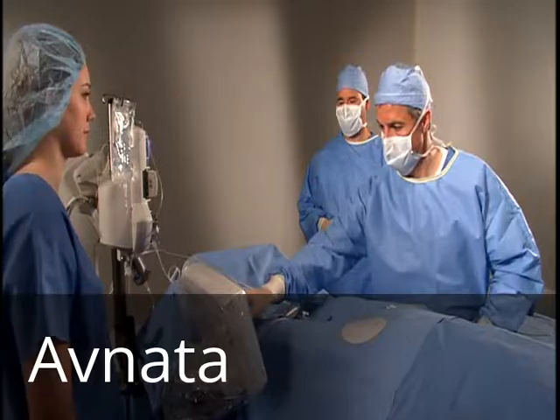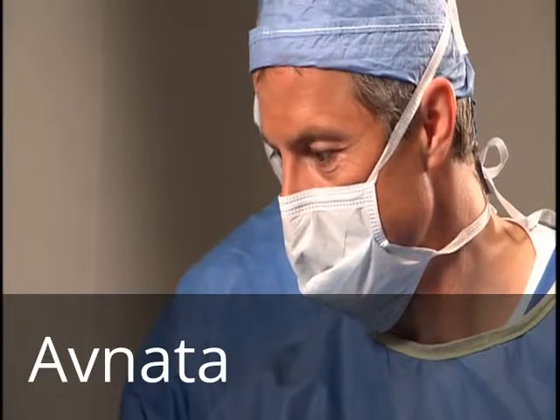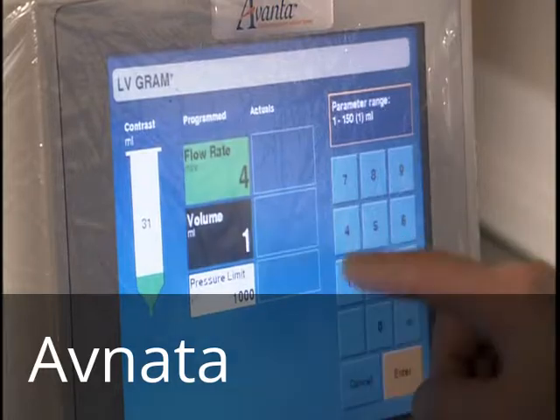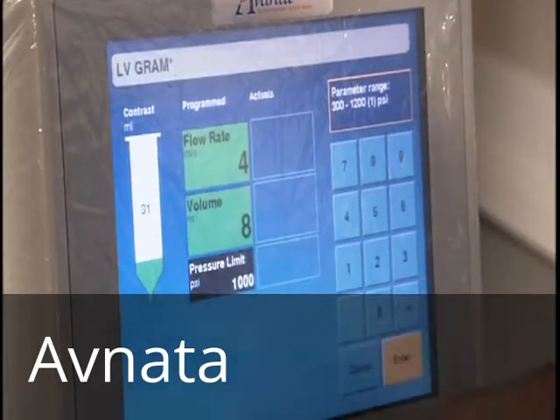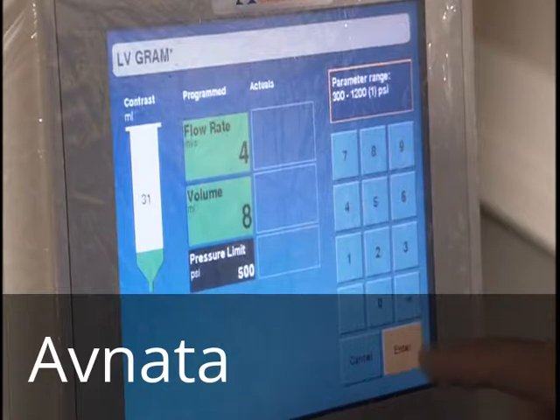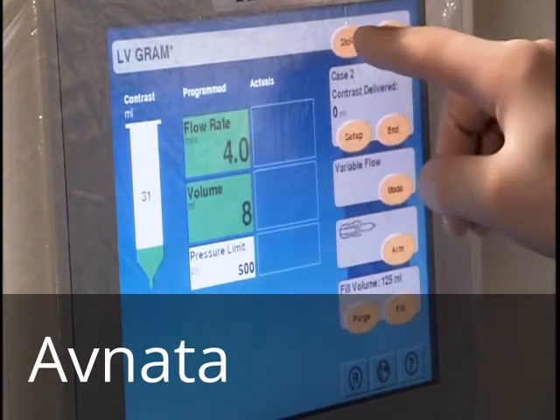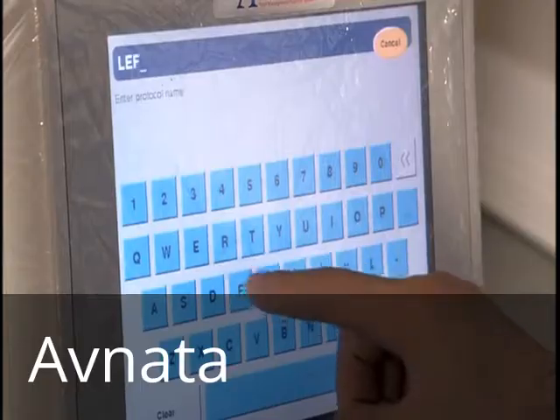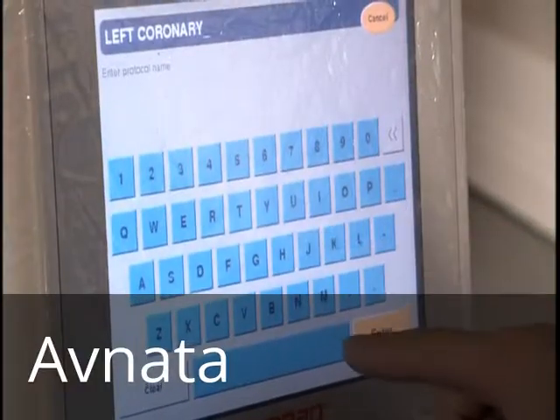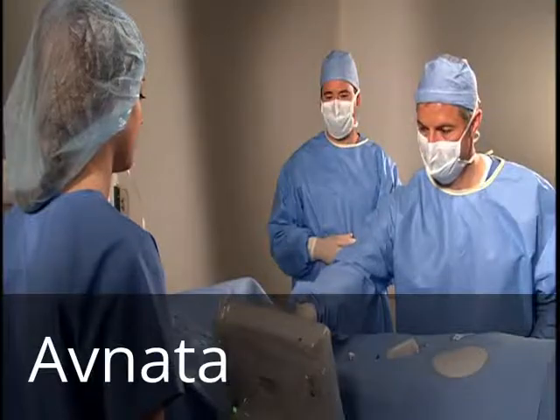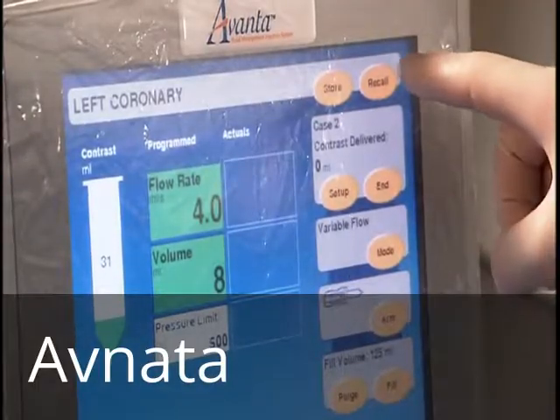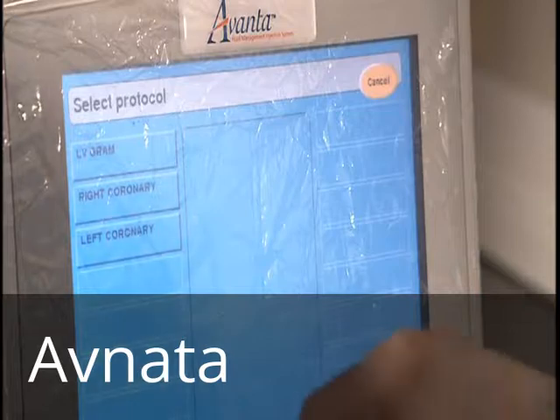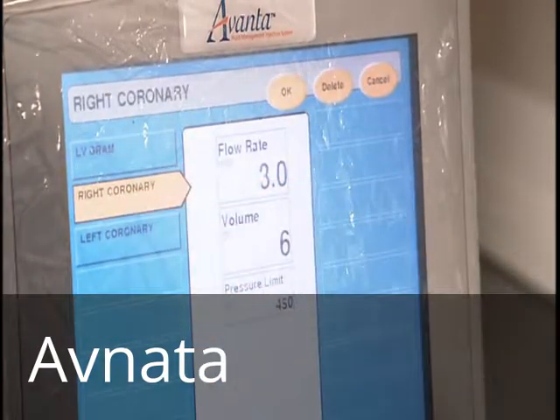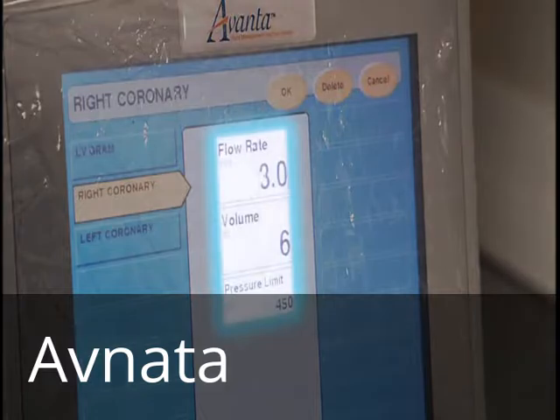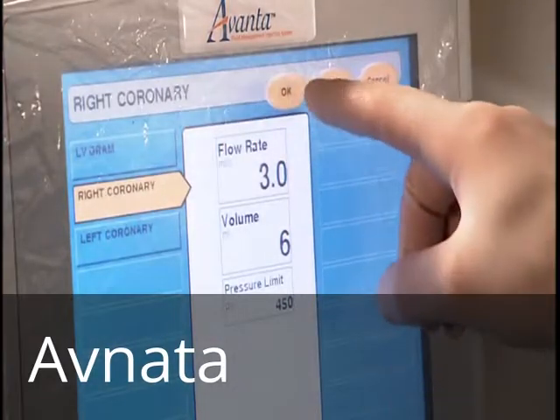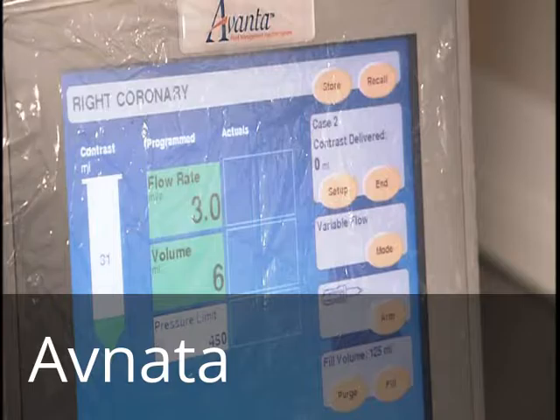The Avanta Fluid Management Injection System allows you to store up to 40 frequently used protocols. On the protocol screen, enter the parameters under the programmed column. Touch Store. Enter a title of up to 20 characters, including spaces, and touch Enter. To recall a protocol, touch Recall. The stored protocols are displayed. Select the desired stored protocol, and the key parameters are then displayed. Touch OK to select the protocol for use, or cancel.